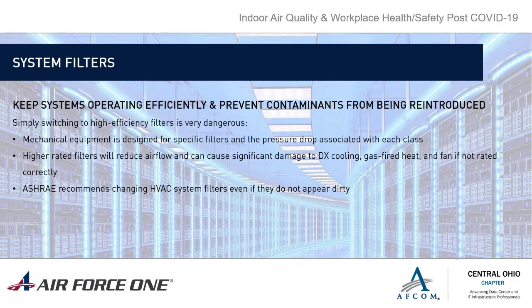So it's something you really have to think about before you just go throw filters in. What are the unintended consequences? One of the points of this slide, the message we've been giving our customers, is that yes, system filters are essential. Maintain quarterly system filter changes, but it's somewhat unnecessary to increase filter ratings from, let's say, a MERV 8 to a MERV 13.